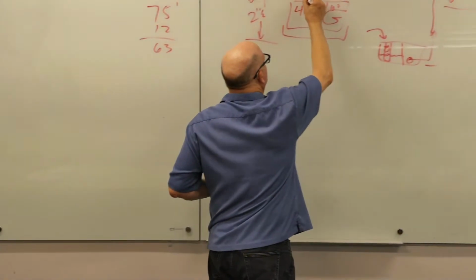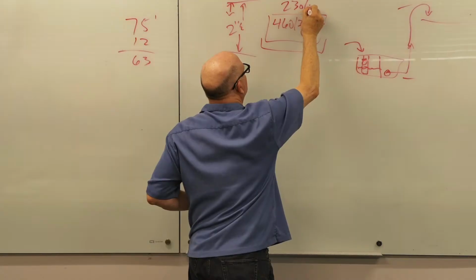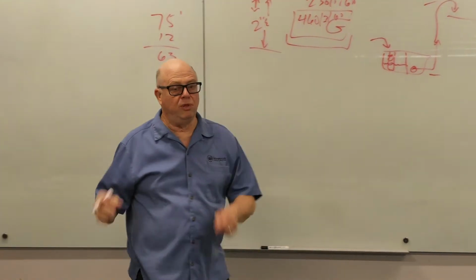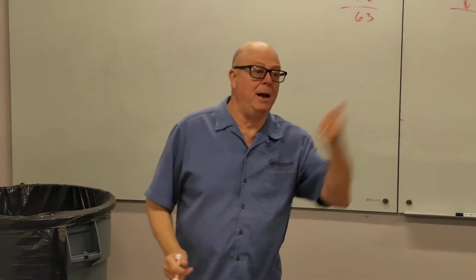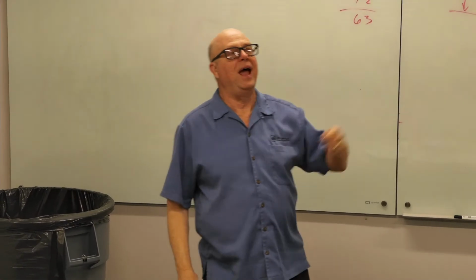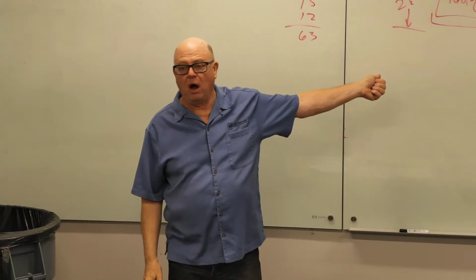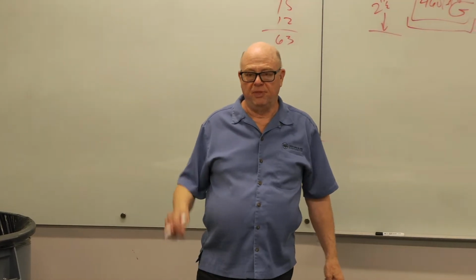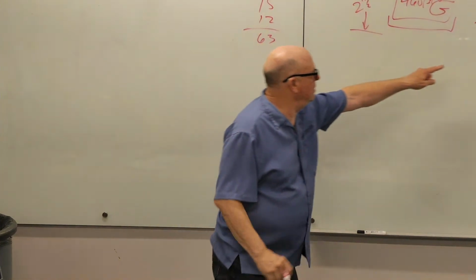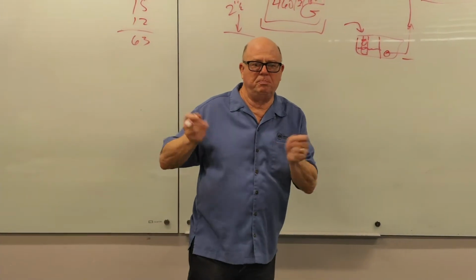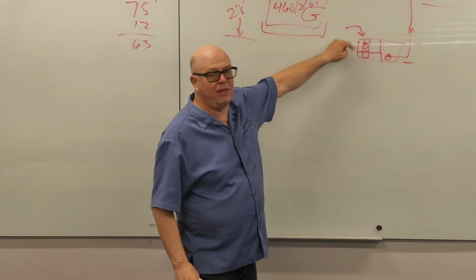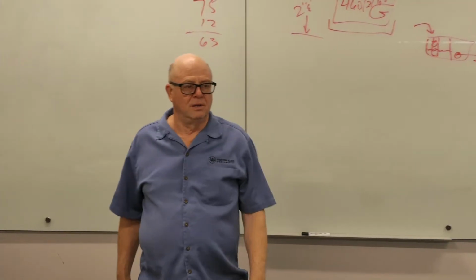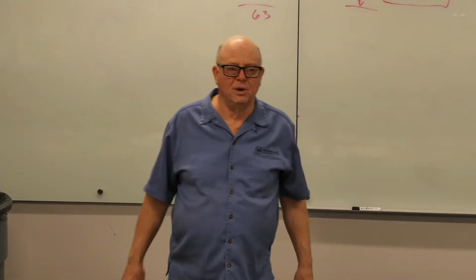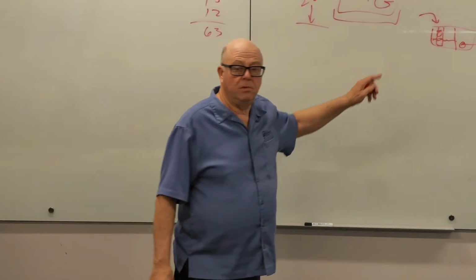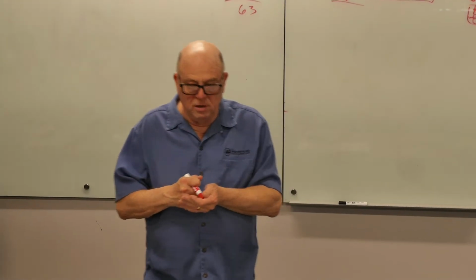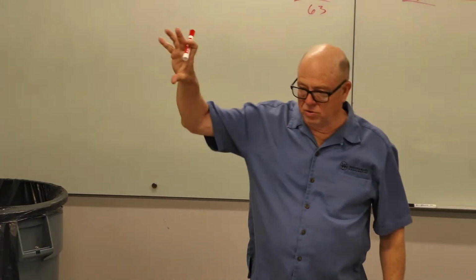If this is 230 single phase, you might simply go with a 230 volt condensate pump and power it right off the unit power. And again, you don't have to put any controls in for it. It's just going by the ping pong ball float. It's not really a ping pong ball, obviously. Okay. So condensate pumps: head and voltage.